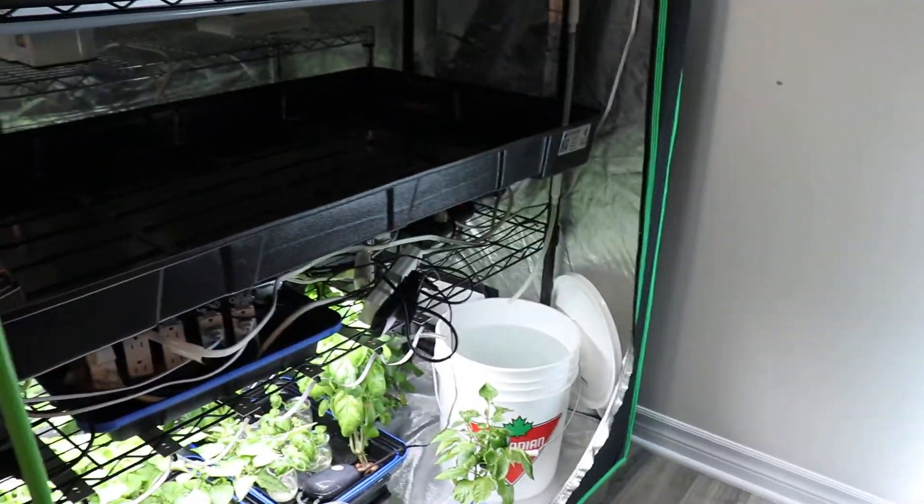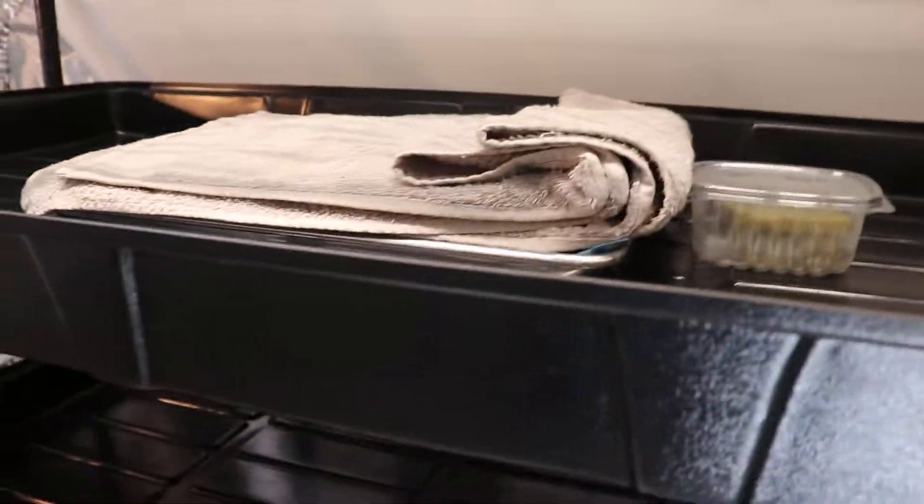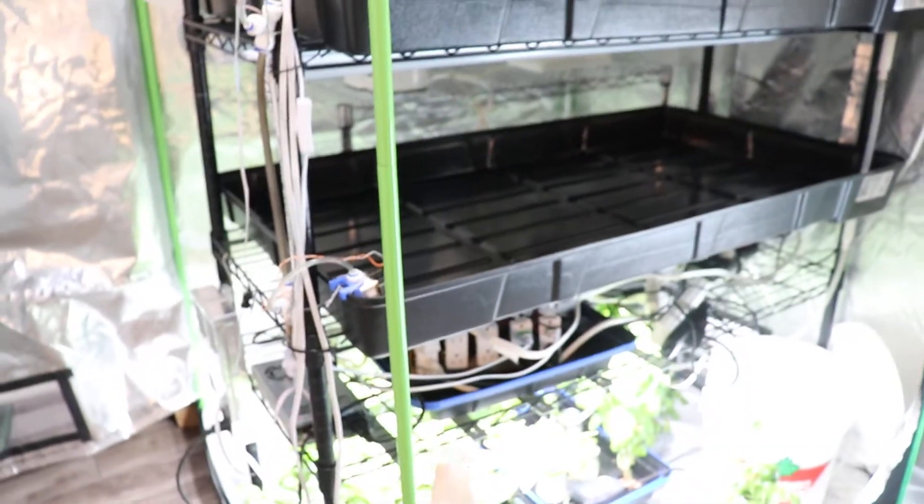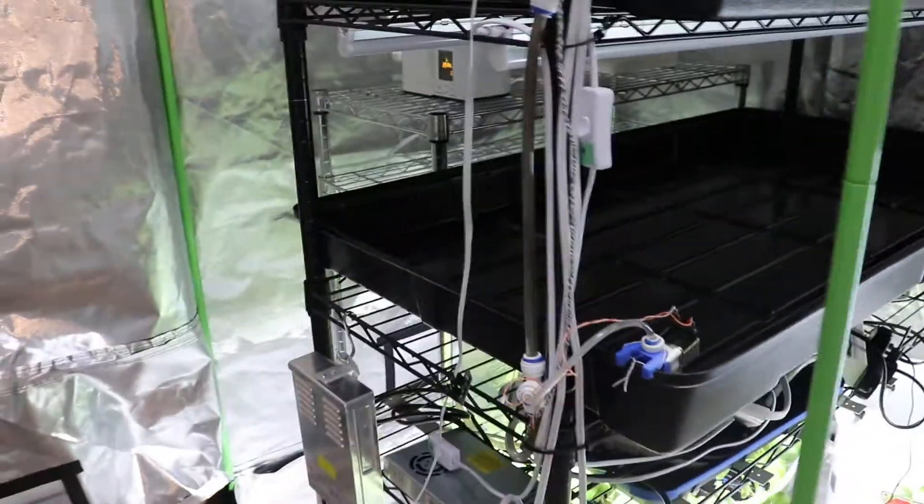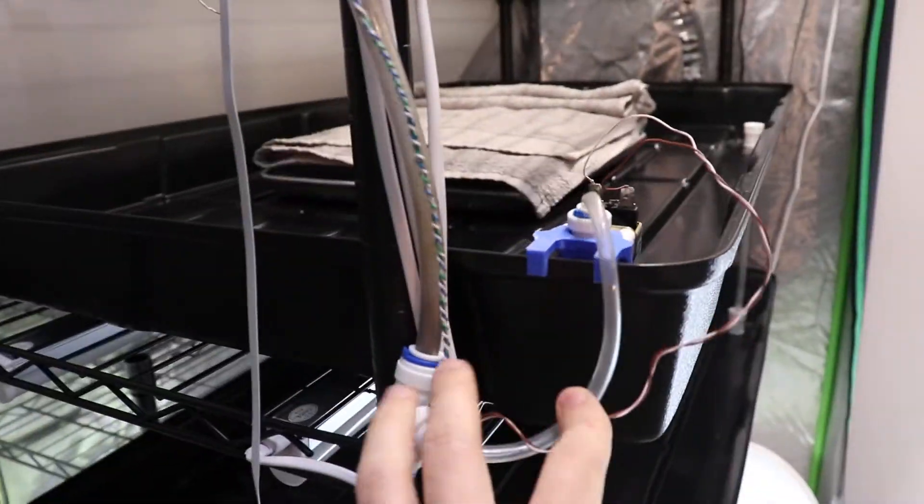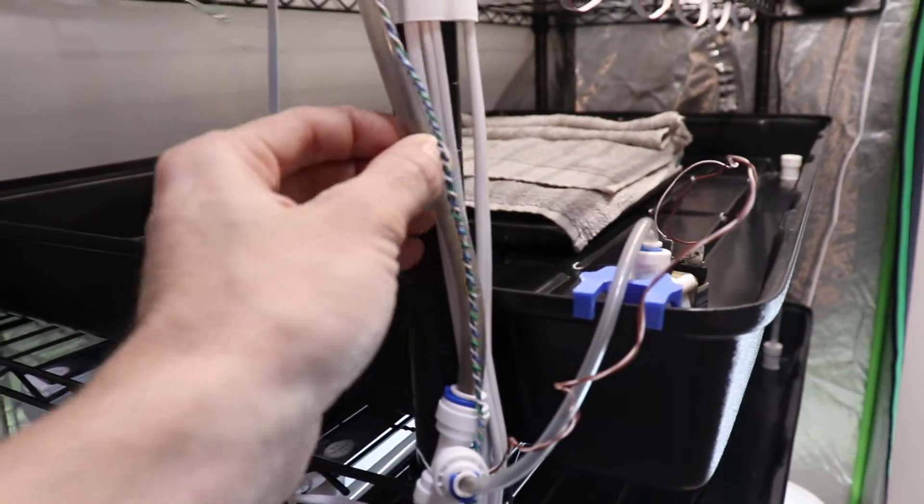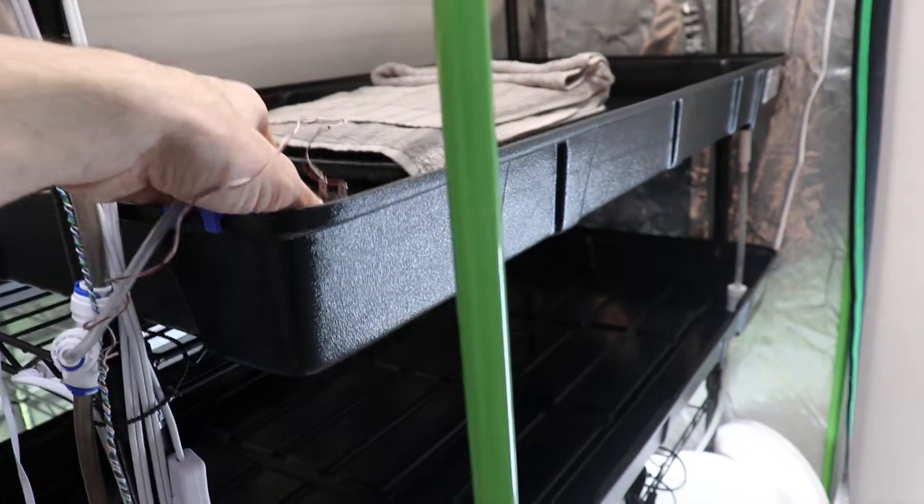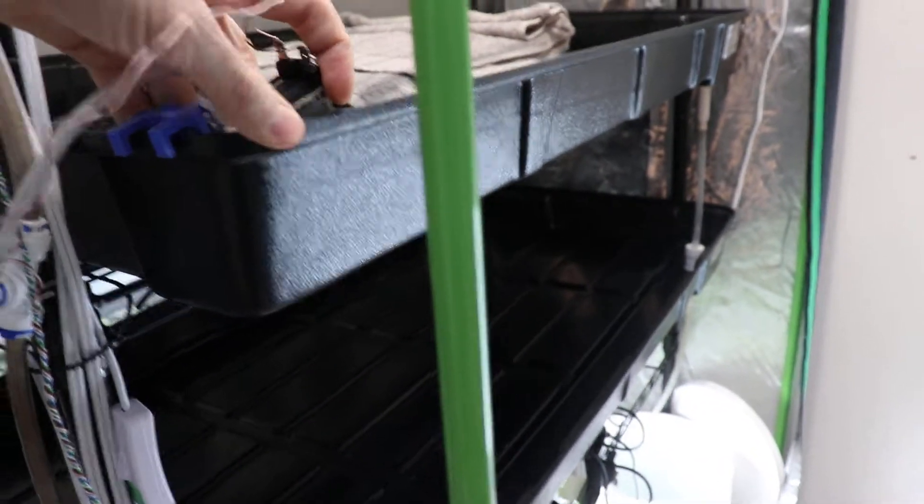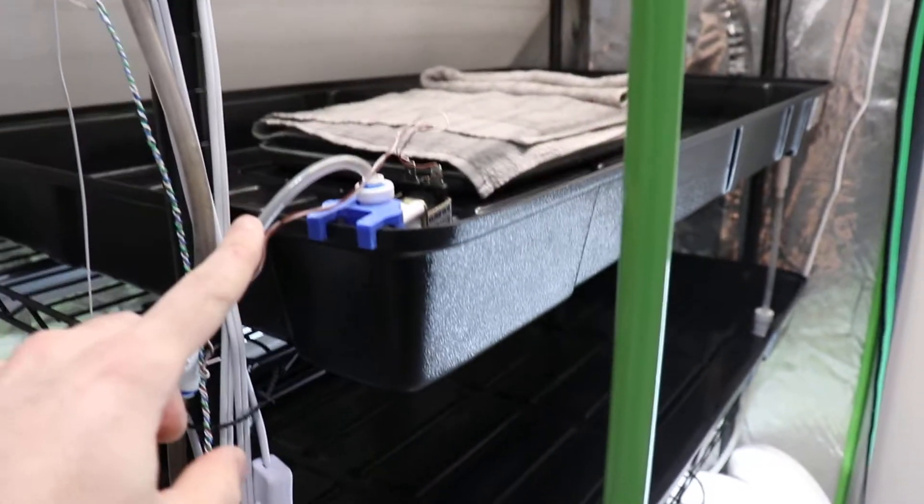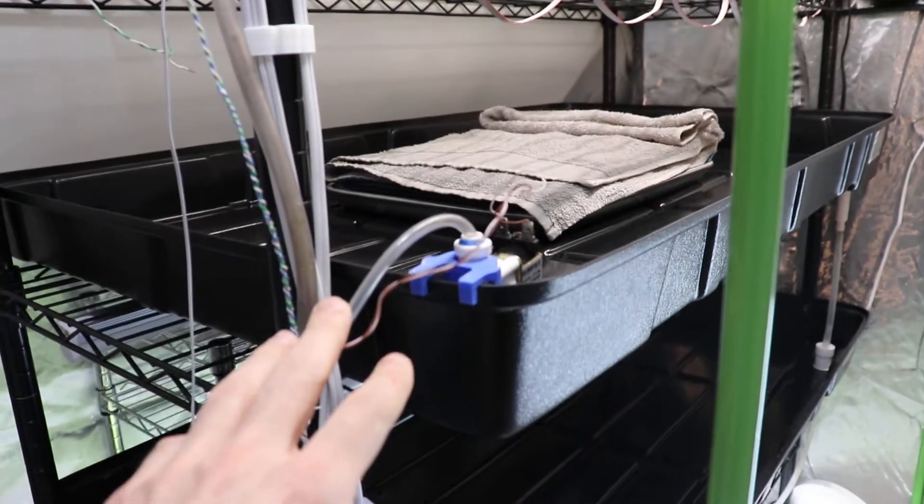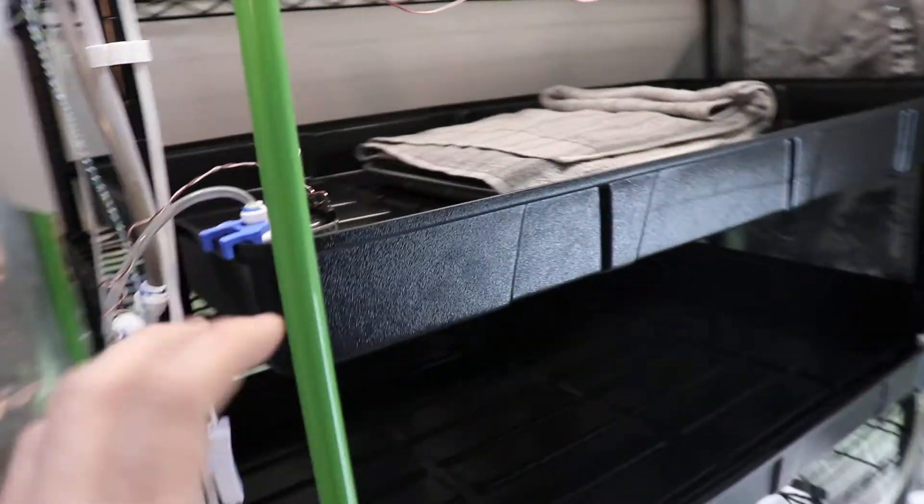Both of these tubes were installed at the same time. Sorry for the audio - the fan kicked in, or actually the air filter. You can see the same thing here: the small tube is clean and the big tube is dirty. So the idea of running these small valves will not only work in terms of being able to control it, but the hygiene aspect I was wondering about is proving to be good.